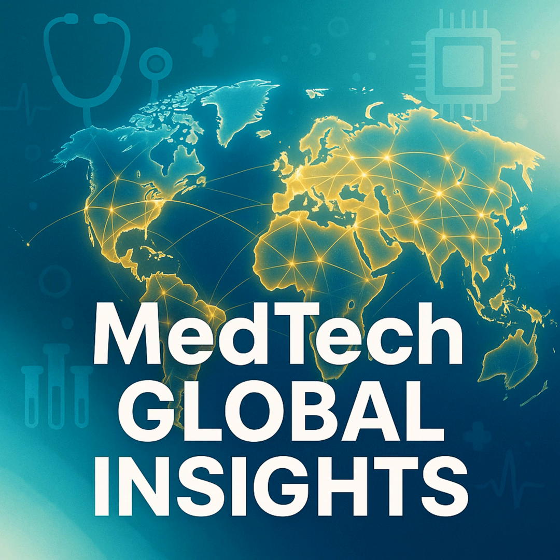The first and most critical step is classification. Under the MDR, most AI-powered software, particularly tools for diagnosis or therapy, are classified as Class 2A or higher. This classification automatically requires the involvement of a notified body for conformity assessment. For instance, an AI algorithm that analyzes radiological images to identify potential tumors would likely be Class 2B, depending on the directness of its diagnostic claim and the risk to the patient.